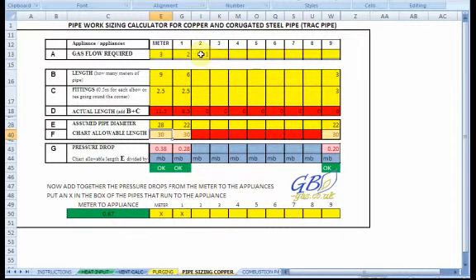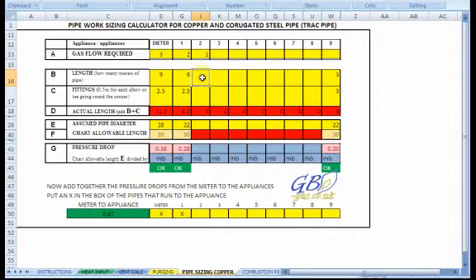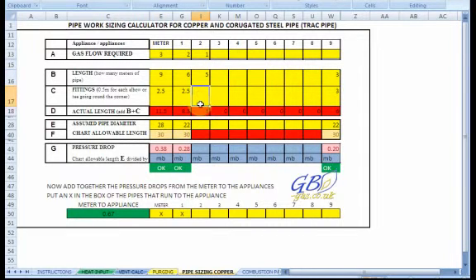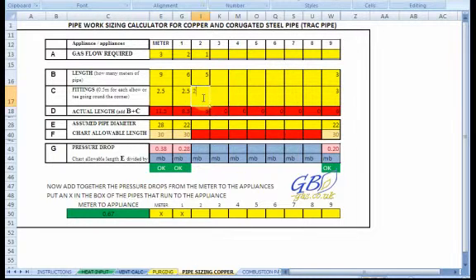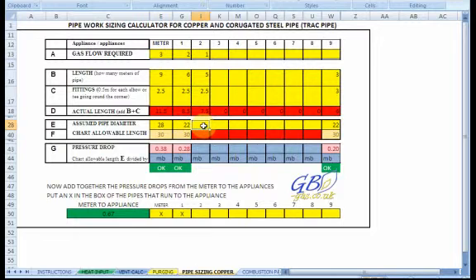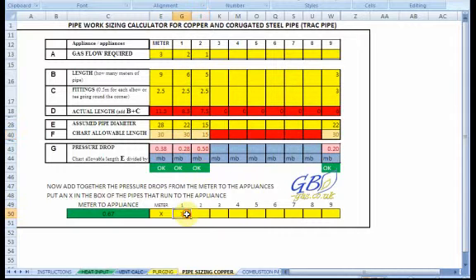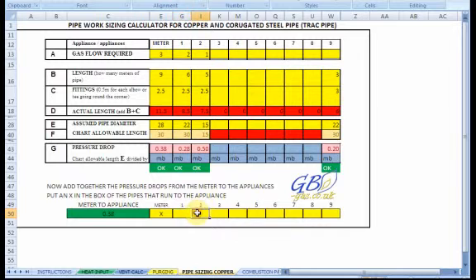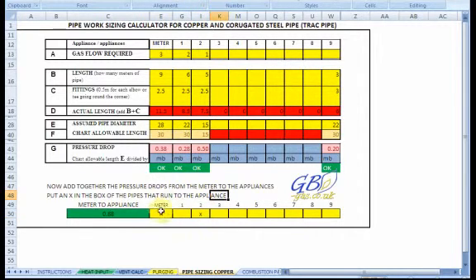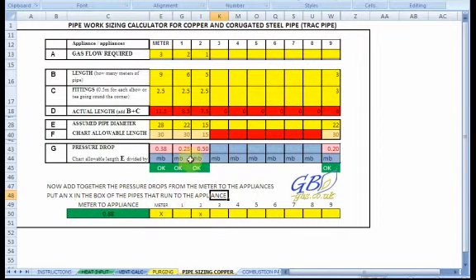This last stage, for argument's sake, going to a cooker, I have got, let's put in five metres of pipe, and I've got four elbows this time, and a tee piece to go round. Four elbows and the tee piece is still going to be 2.5 metres. And we're going to assume that it's 15 millimetre pipe this time. Once we work that out, we've now got half millibar drop for this bit of pipe work. So, if I add the two X's together, that X and that X there, from the metre to appliance 2, I've got a 0.88 millibar drop. And because it's less than 1 millibar, it's all OK.